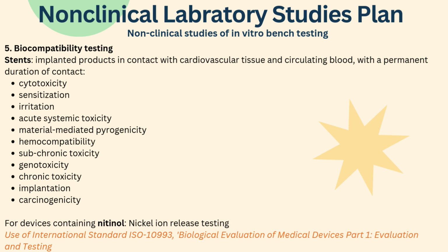Because this stent is in continuous contact with blood, we will also be ensuring that hemocompatibility testing is done. Again, this is paramount to evaluate the risks, which may include thrombosis or other adverse coagulation responses. Furthermore, the implantation studies will work to assess the tissue response at the specific implantation site over time, which could include inflammation and healing. Again, another important note to consider is that for devices containing nitinol, additional nickel ion release testing is going to be conducted just to evaluate the potential hypersensitivity or possible toxic effects related to that specific metal ion leaching.